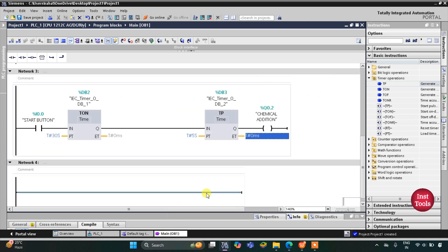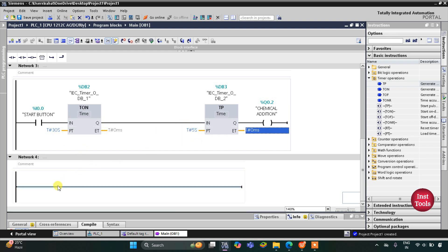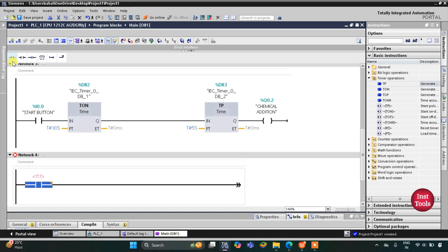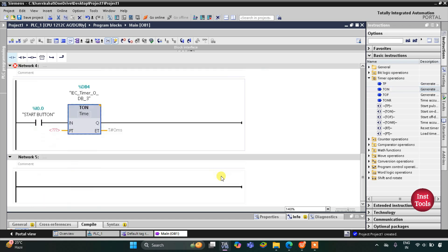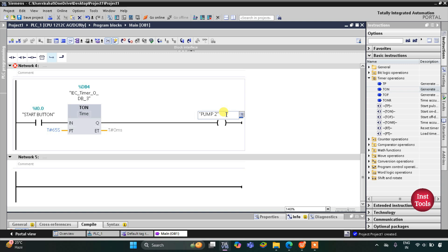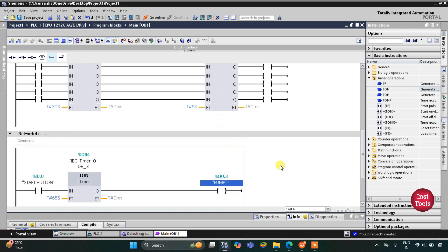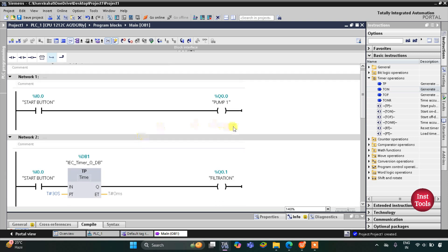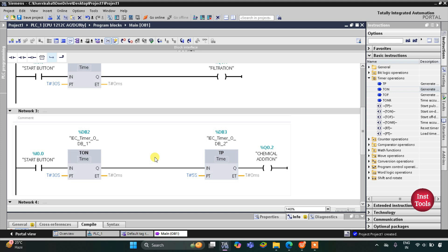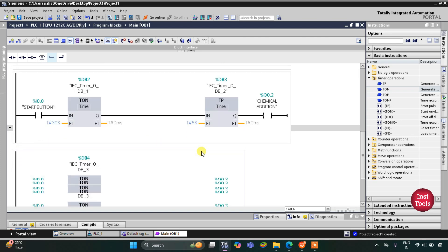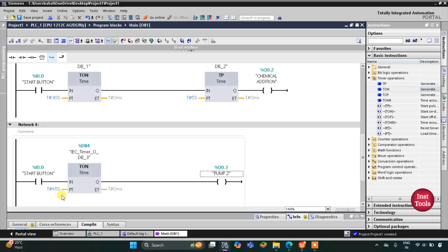After 30 seconds plus 5 seconds — that is after 35 seconds — pump 2 should turn on. When the start button is turned on, there will be an on-delay timer with a preset value of 35 seconds, and after 35 seconds pump 2 will get on. So when the start button is turned on: water is transferred by pump 1, filtration runs for 30 seconds, chemical addition runs for 5 seconds, then pump 2 gets on after 35 seconds.